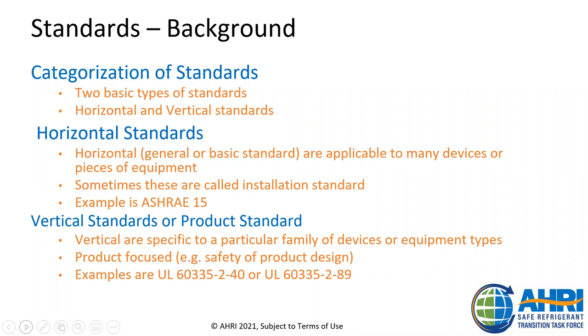The national deviations adopted in the UL standard, for example, are stricter than the IEC standard, which is already a good strict standard. On top of that, multiple standards can be applied to an installation because of this horizontal and vertical setup. So for example, a manufacturer makes a piece of equipment. First, it will need to be safety listed to an ANSI accredited national safety standard. In our case, it's the UL 2-40, which is a vertical standard. And just to be clear, safety listing means it's a third-party lab certification for safety of a product to a nationally acceptable safety standard. So it is being listed to a vertical standard. And then when it is installed in a building, it needs to be done so in accordance with another safety standard. In the case of air conditioning heat pump, again, it is the ASHRAE standard 15, or it could be a building code, which generally adopts the ASHRAE 15 standard, and that is a horizontal standard. So this is analogous to a belt and suspenders theory. Next slide.